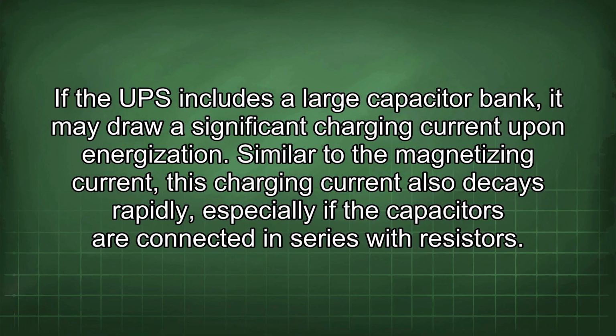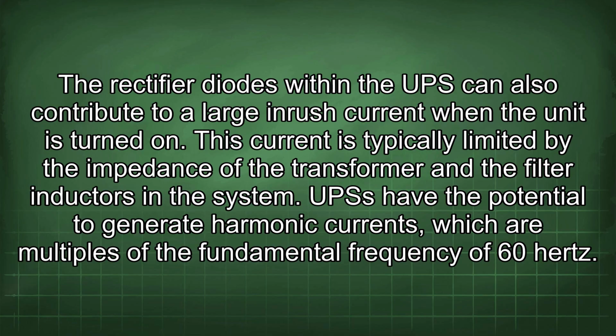If the UPS includes a large capacitor bank, it may draw a significant charging current upon energization. Similar to the magnetizing current, this charging current also decays rapidly, especially if the capacitors are connected in series with resistors. The rectifier diodes within the UPS can also contribute to a large inrush current when the unit is turned on. This current is typically limited by the impedance of the transformer and the filter inductors in the system.